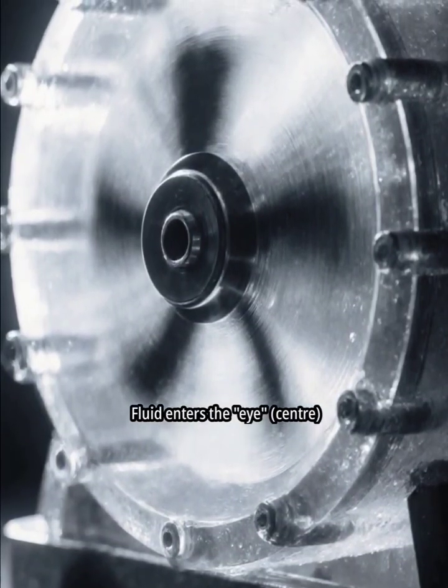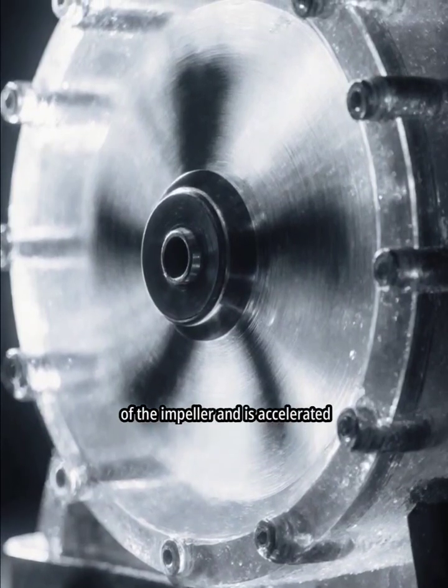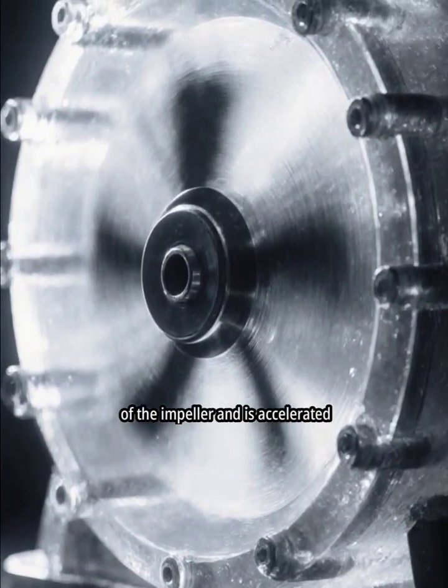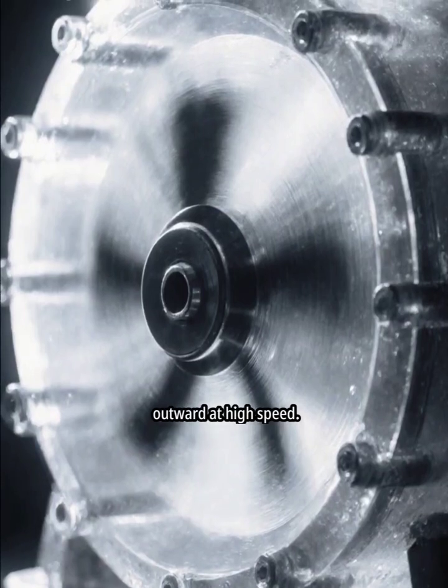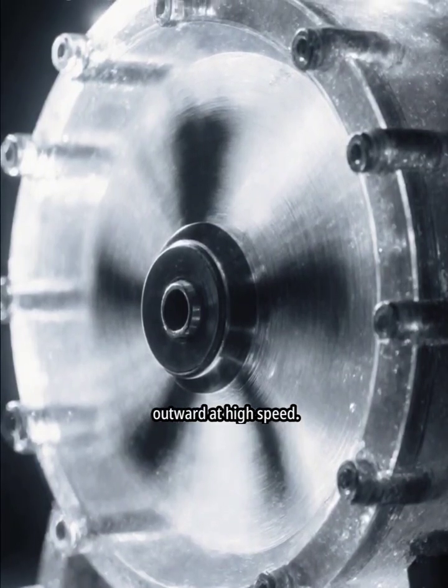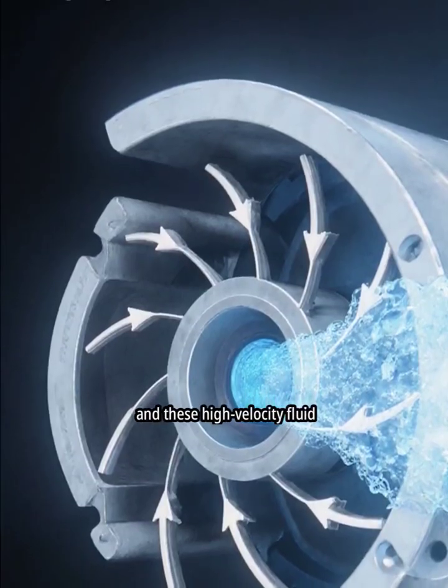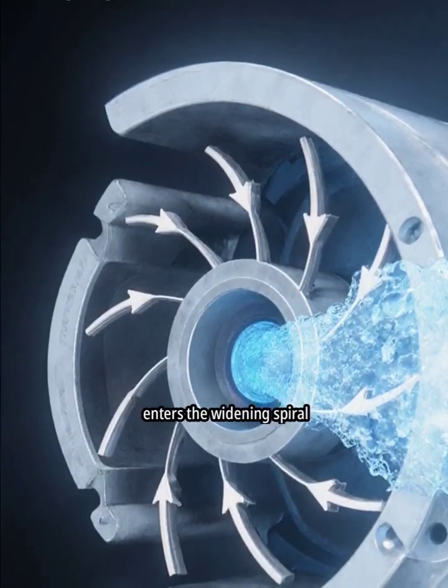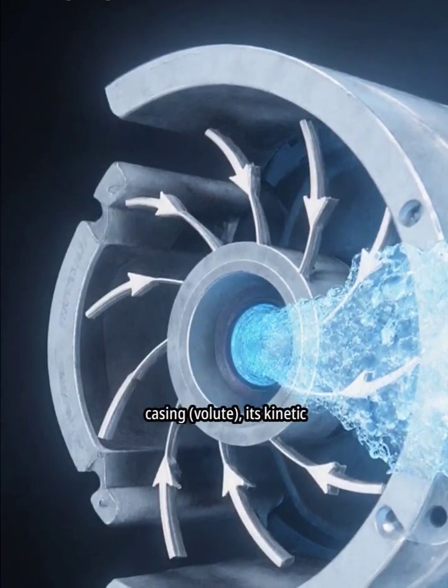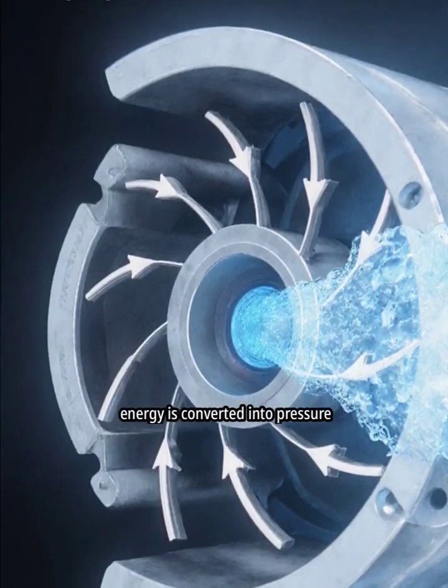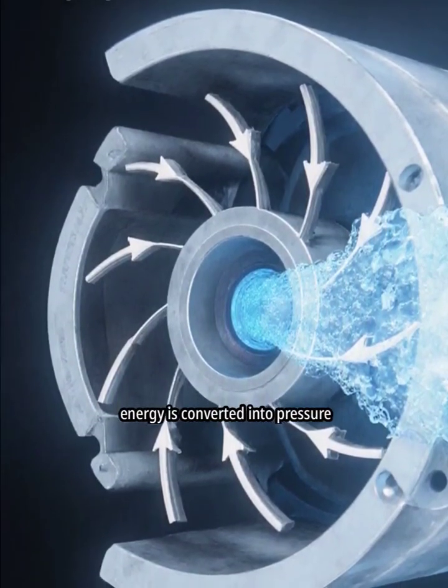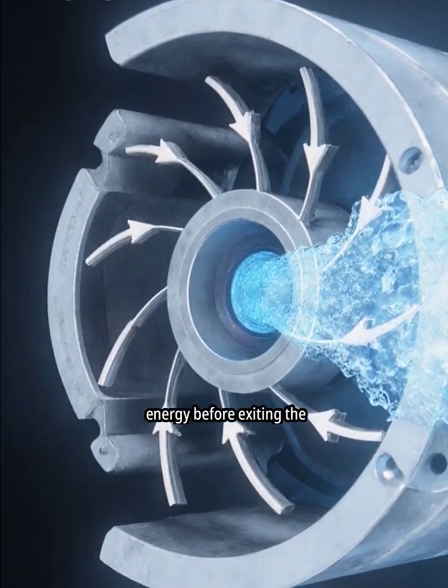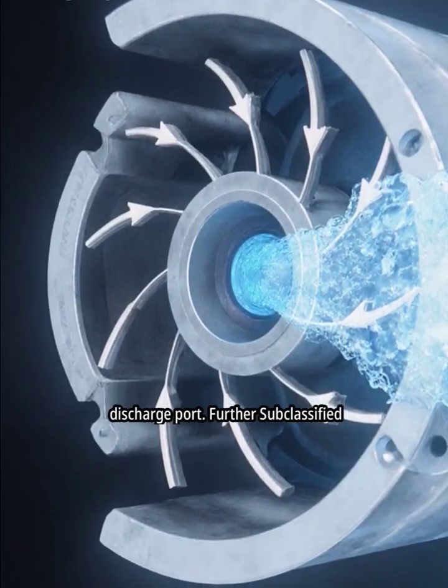Fluid enters the eye, the center, of the impeller and is accelerated outward at high speed. And this high-velocity fluid enters the widening spiral casing, the volute. Its kinetic energy is converted into pressure energy before exiting the discharge port.